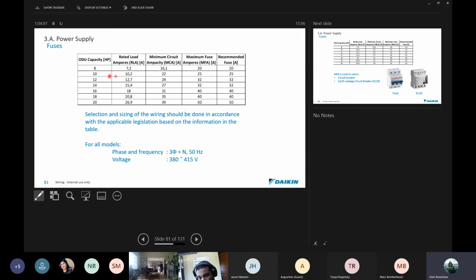The type of things that you'll see on the units, outdoor unit capacity, say for a 10 horsepower, is its rated amperes or run load amps, 10.2, minimum circuit amps is 22, maximum fuse is 25, and the recommended fuse is 25. What do they mean by recommended fuse? Well, we don't have to install fuses, and this has also become confusing. We've seen guys that have tried to install fuses instead of circuit breakers. Fuse is an old term, but by modern terms, we use circuit breakers.